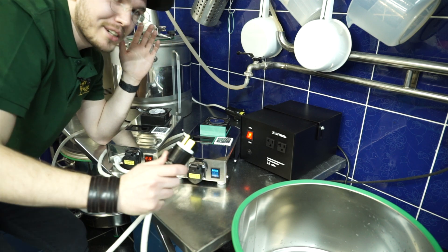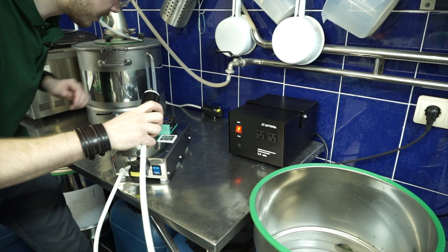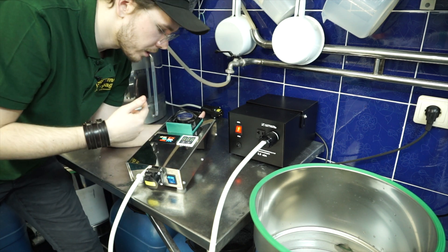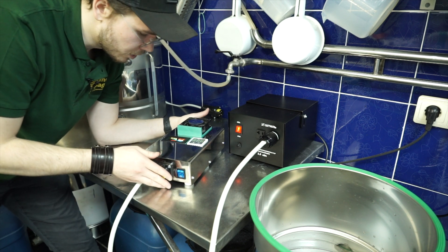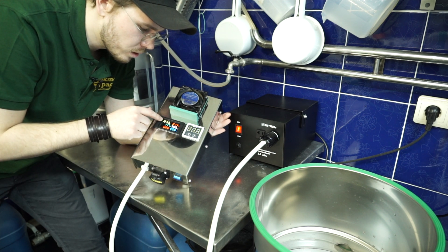If you're a good electrician, write any comments you like. Let's plug it in. You can probably hear that the fan started working — it operates always, and that's fine. You can probably see the parameters on the display: the voltage, 123 volts, and 17 watts — so the fan and the controller are taking some power, about 17 watts.